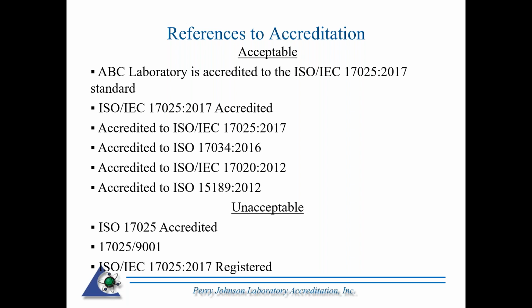That's not correct. It's accreditation. It's not certified. And also unacceptable, just blanket stating 17025 or ISO 17025. It has to state the entire standard, ISO/IEC 17025:2017, accredited.